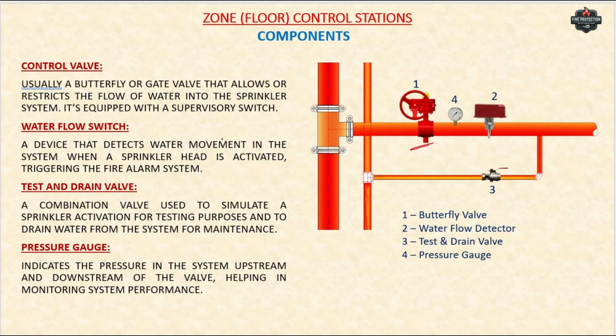Understand? Now the next component is this water flow switch, also called water flow detector, which detects the flow of water. Basically this device detects the movement of water in the sprinkler system. So when a sprinkler is activated or some fire happens, water starts flowing here, and this will detect the flow of water. This flow switch will send a signal to the building fire alarm panel, which will alert occupants and the emergency responders like some AFF or fire brigade people.